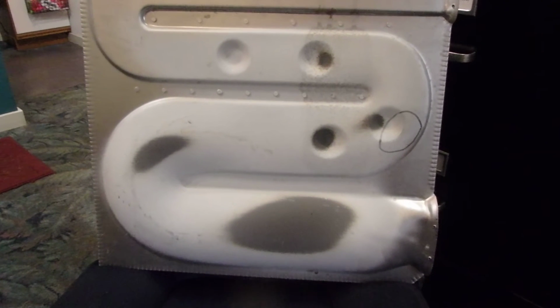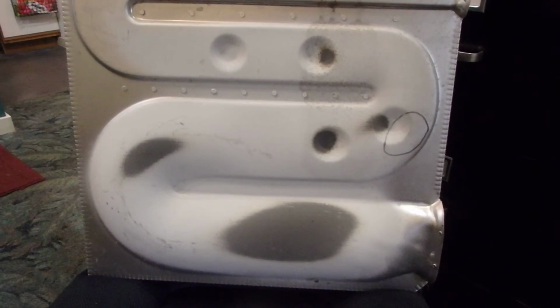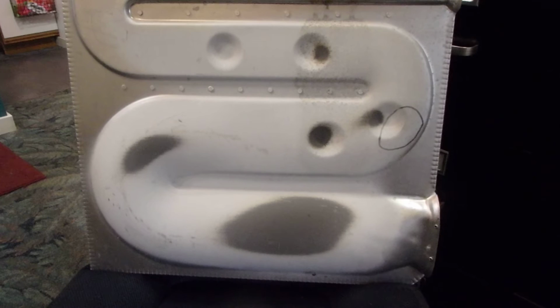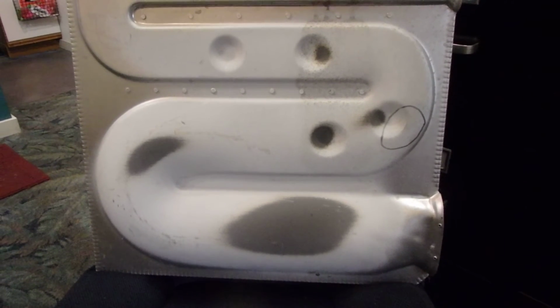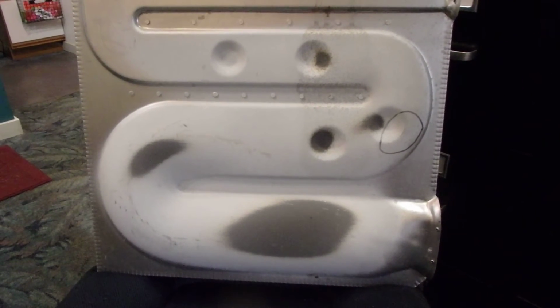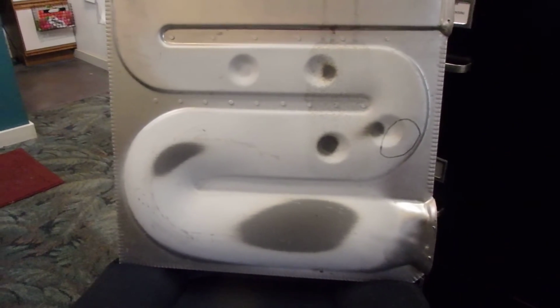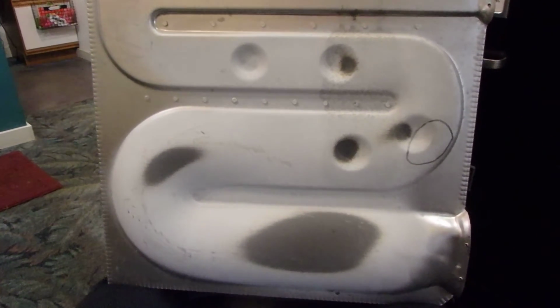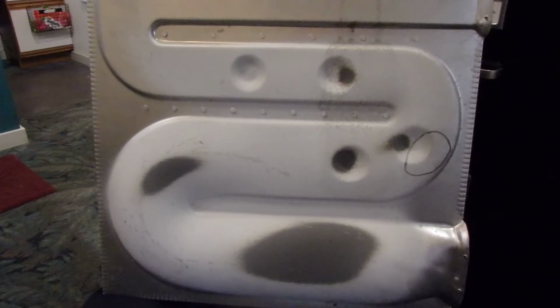We worry about heat exchangers because they're metal, obviously, and they go from very cold to very hot, back and forth very frequently. And when you do that with metal, it can fatigue and it can crack. When you get a crack in the heat exchanger, you do run the possibility of getting carbon monoxide.